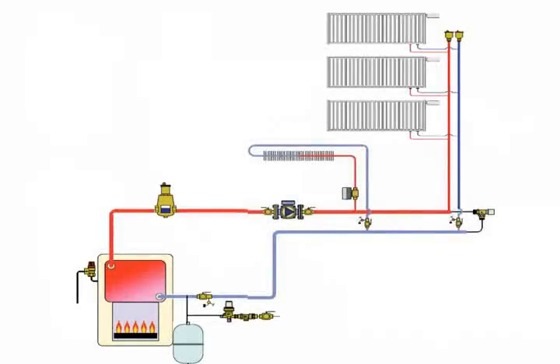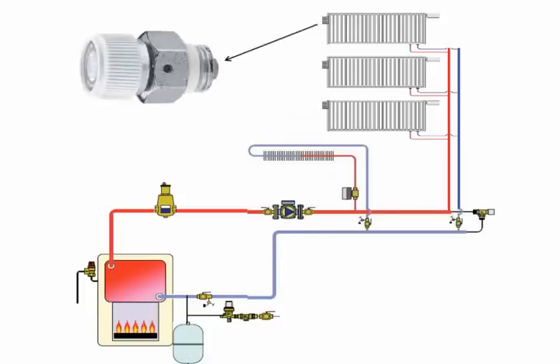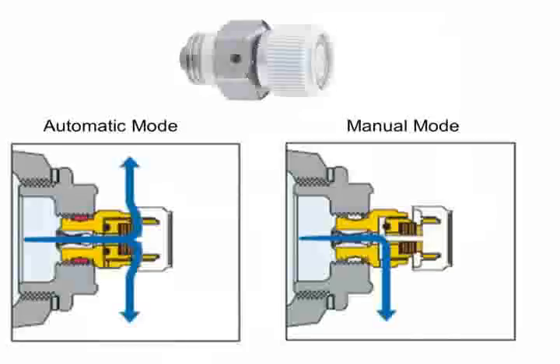Now this little guy down here is worth talking about, and this is a hygroscopic air vent. And why is it worth talking about? If we go back to our diagram where we had these float type air vents, what are they trying to do? They're trying to get rid of the air that goes up in the riser so it doesn't create havoc in our heat emitters, okay? Alternatively, we could have gotten rid of those floats, and right on the heat emitters themselves put in an air vent such as this.